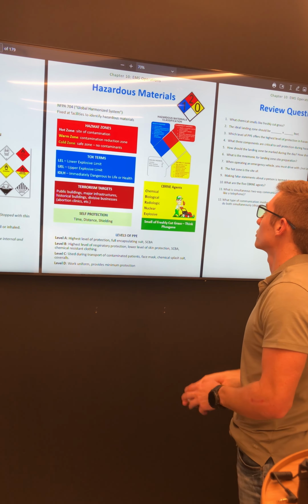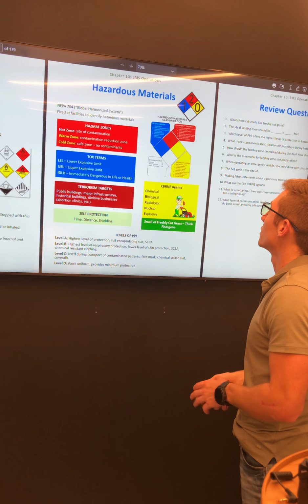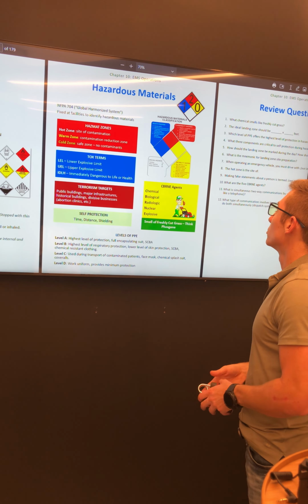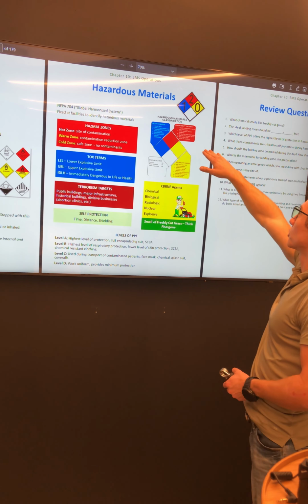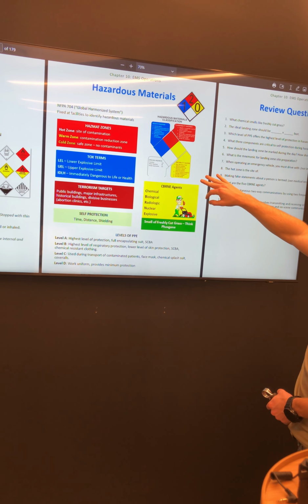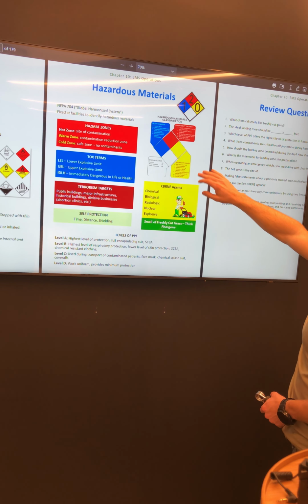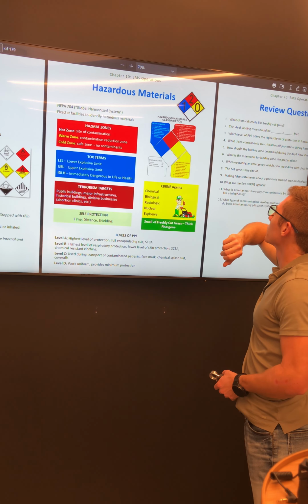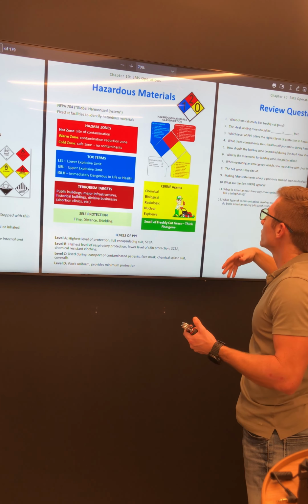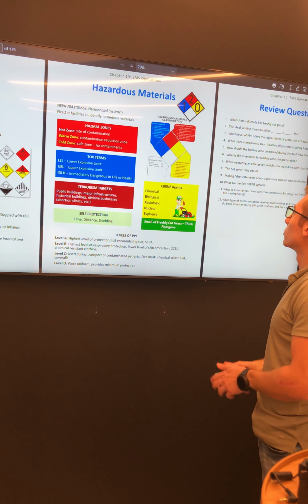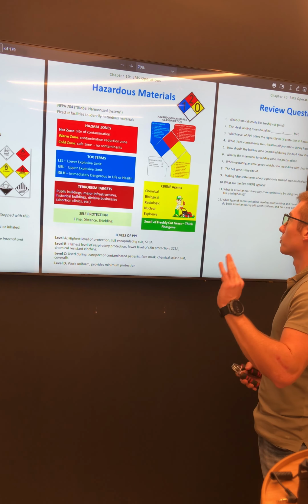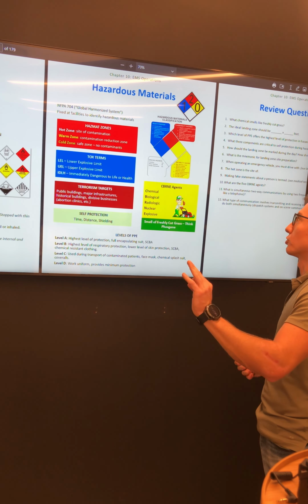0, ordinary combustibles, no hazard beyond. Flammability hazard, 4, rapidly or completely vaporize and burn readily. 3, it ignites readily in ambient conditions. 2, ignites when moderately heated. 1, requires preheating for ignition. 0, will not burn under normal circumstances.